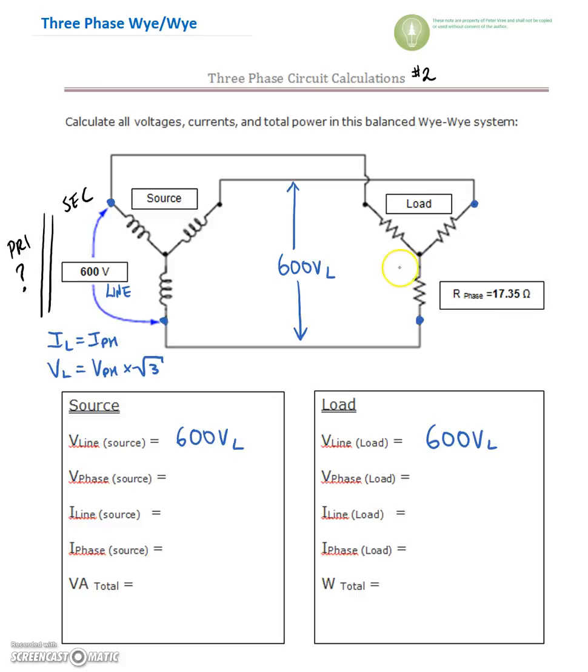So our phase voltage, which is the voltage on the inside, that voltage right there we're going to find by taking 600 volts on the line, and we're going to divide that by root 3. Now it should be 347, right, because we've already memorized those equations.